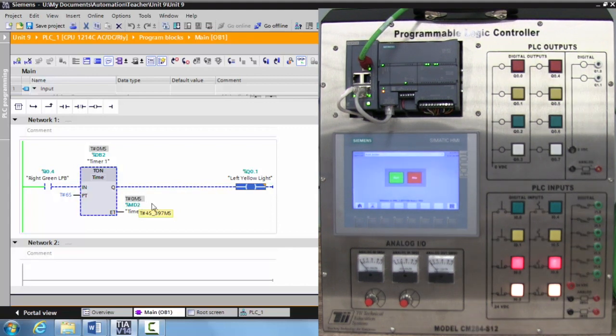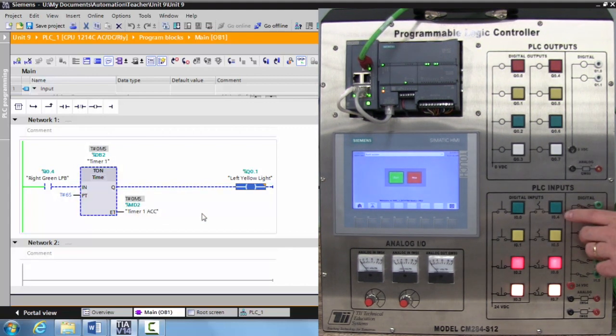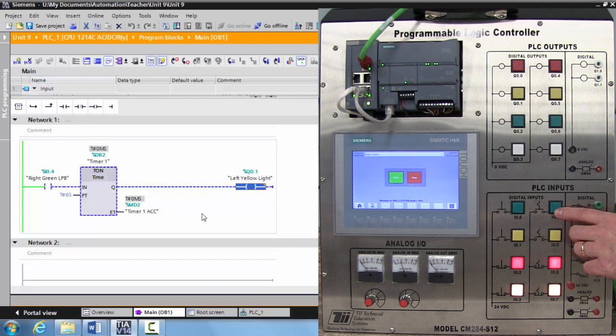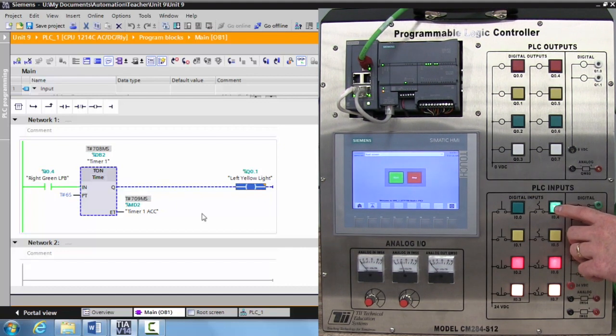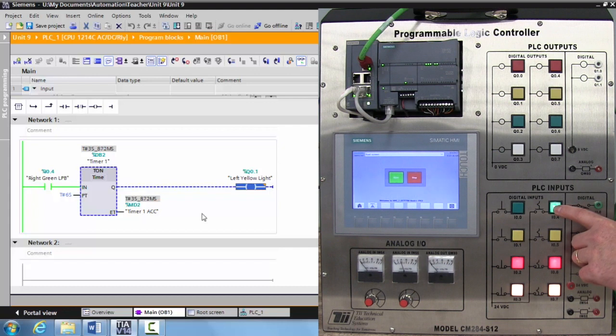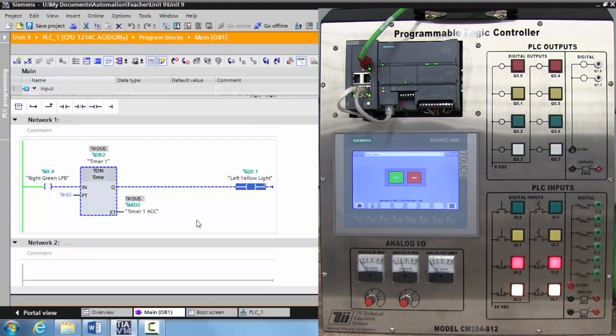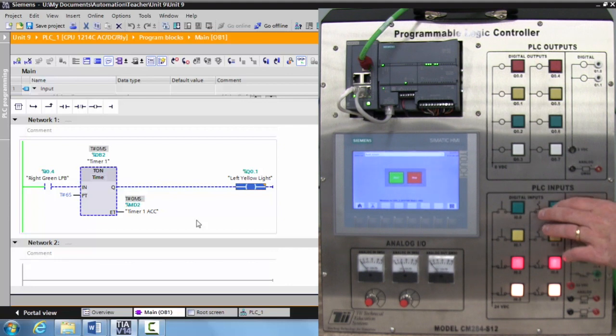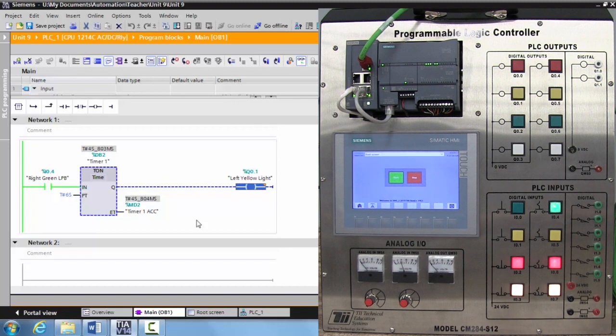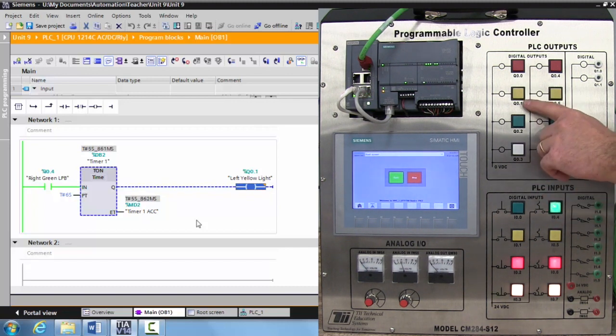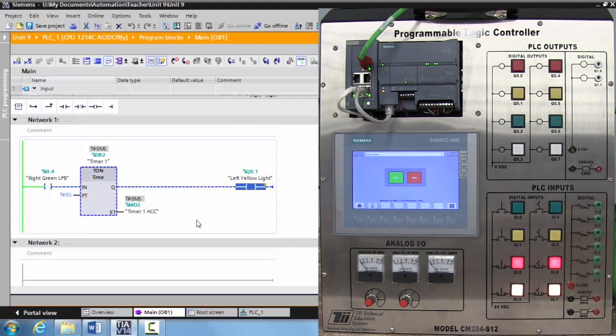Now let's explore a little bit about how this timer works. You hit the green button here, it starts timing. If the logical continuity is cut off to the input of the timer before it reaches that six seconds, the yellow light will never turn on. You activate it, wait six seconds, and then the yellow light activates.